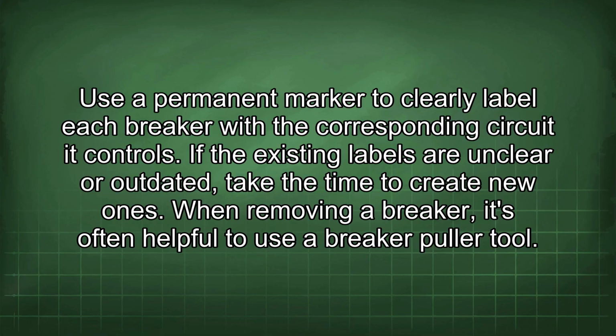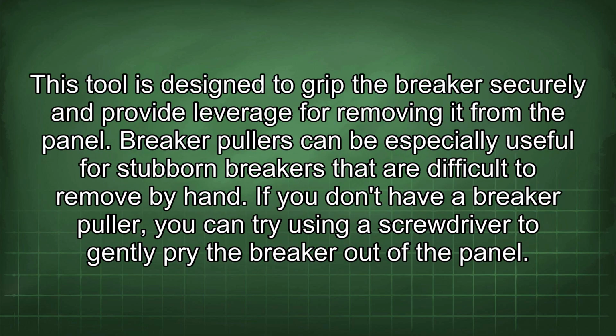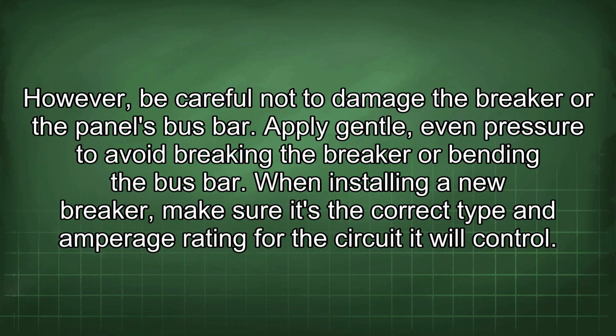When removing a breaker, it's often helpful to use a breaker puller tool. This tool is designed to grip the breaker securely and provide leverage for removing it from the panel. Breaker pullers can be especially useful for stubborn breakers that are difficult to remove by hand. If you don't have a breaker puller, you can try using a screwdriver to gently pry the breaker out of the panel. However, be careful not to damage the breaker or the panel's bus bar. Apply gentle, even pressure to avoid breaking the breaker or bending the bus bar.